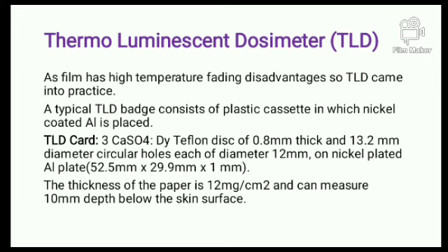TLD means thermoluminescence, emission of light dosimeter. When you heat the disc, at that time only it is going to emit light, luminescence, and it is going to give you the records. Did you understand? TLD means thermoluminescent dosimeter. Thermo means heat. Whenever you heat this TLD disc it will emit light, and that light will be converted to signals, and those signals will tell us how much dose an individual has received.